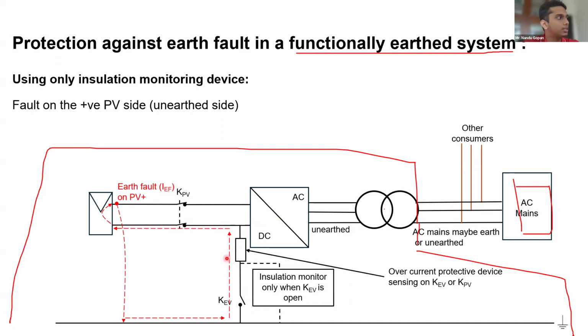The point in this system earthing is that it will inform the maintenance person or whoever is there that there is a fault here and you are supposed to rectify it as soon as possible. And this insulation monitoring device will also open when this works. So when you want to do any maintenance work, you will have to disconnect here, and the insulation monitoring device will also work. And in most PV sources, before energizing and after the day's operation, you are supposed to check the insulation monitor for the value, to see if there is any weak insulation or not. So this is how the earth fault protection is done.